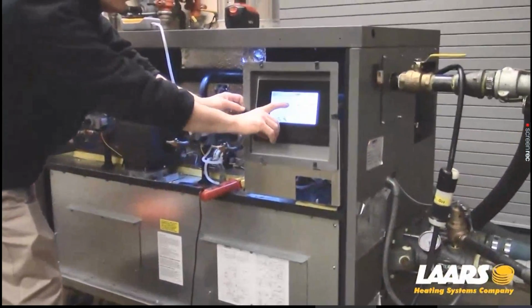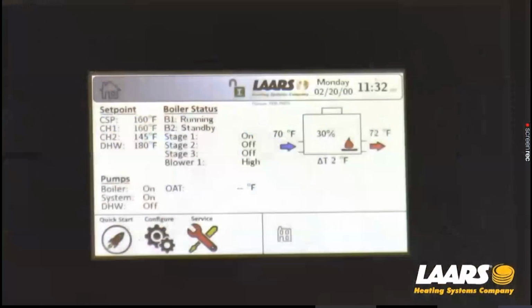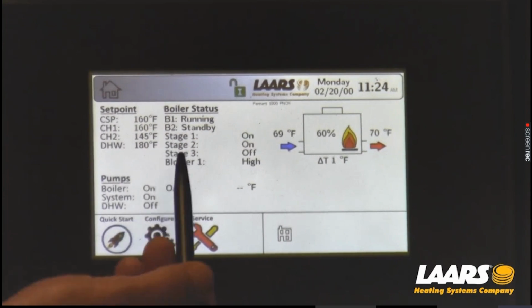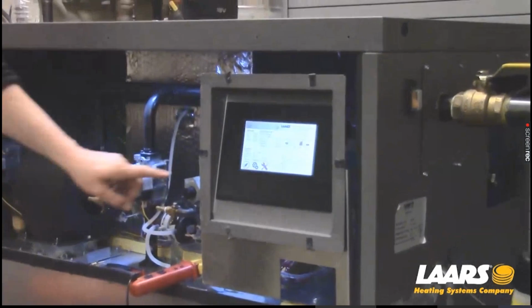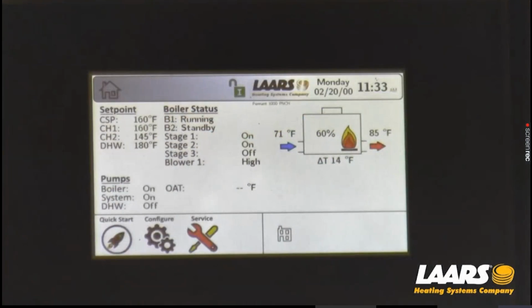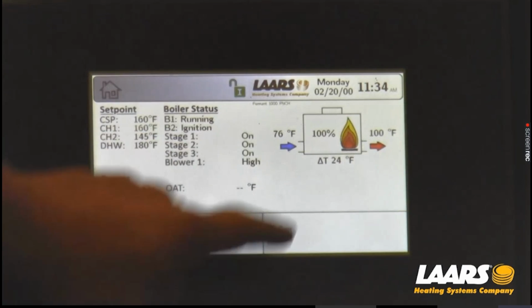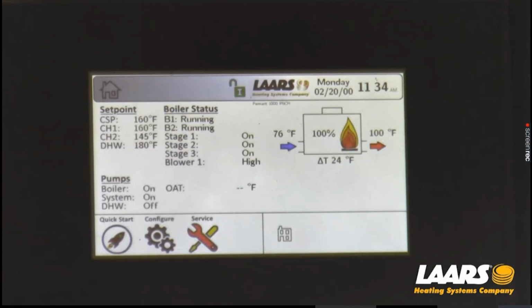So, as you can see, stage one is on. We're firing at about 30%. This is a 1 million BTU boiler. I want all three valves in the on position to do combustion test. Stage 2 is coming on. Stage 3 should be firing shortly. It's showing B2 on the HSI warm-up. And now stage 3 is on. We're at 100% of fire. Now we can do combustion testing.